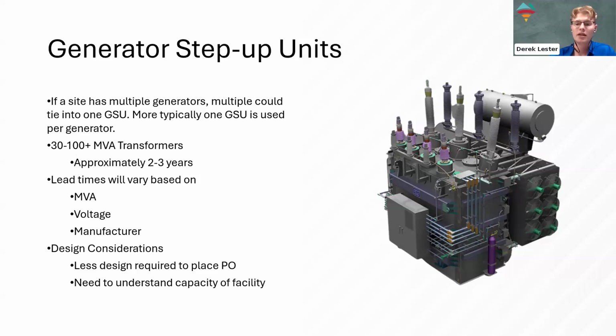The other factor is voltage. The higher the voltage on the high side of the transformer, the fewer facilities have the capability to test those once manufactured, so there's a thinner market and longer lead times.